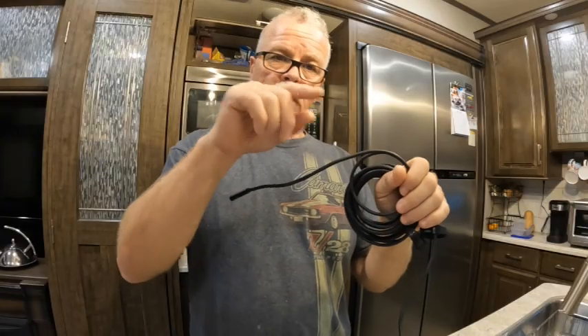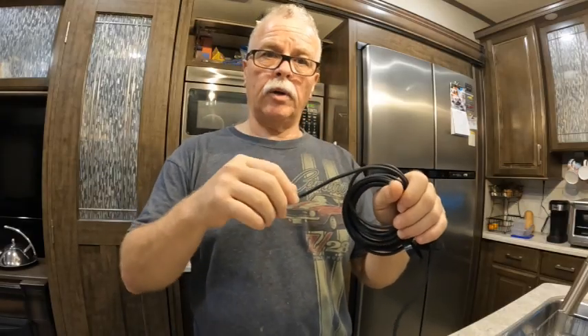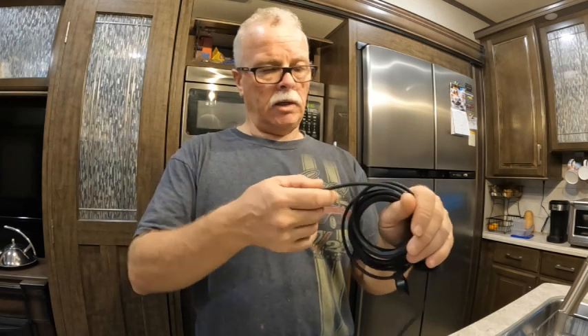You can retrieve it. Now I'm going to show you when we stick it into the hot water heater through the anode hole so you can see what it looks like. So there's some water — look at all that crud right there. That's before flushing. You can see all that crud, and right there you can see the heating element — it's got some stuff on it. Then we'll see what it looks like after the flushing and after we do the vinegar wash.